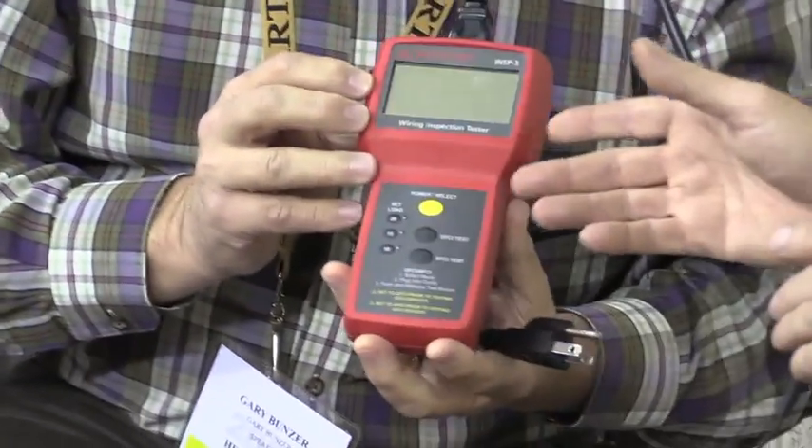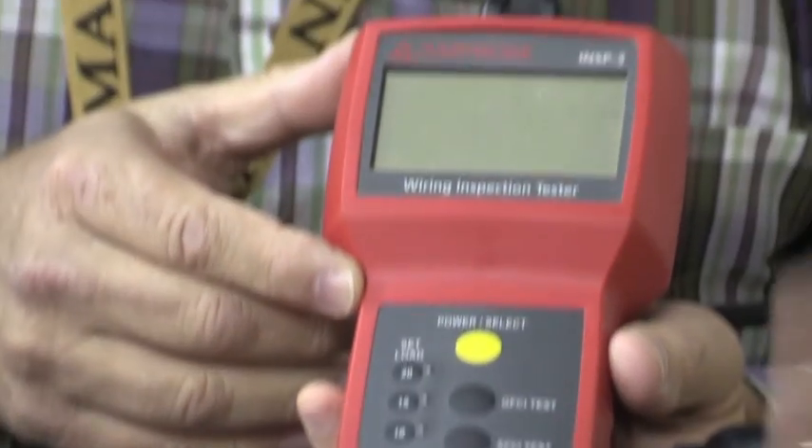Anything plugged in with a grounded plug — from a toaster to a guitar amp to your RV — could create a deadly condition. Even a very expensive ground loop impedance tester won't find this issue. A $300 commercial outlet tester will also tell you polarity is okay. Modern surge protectors won't discover it either. Mike went through every major manufacturer — Fluke, Triplett, Amprobe — all of whom thought their gear could detect this, and he sent them videos proving it couldn't. Nobody ever told them this was possible.